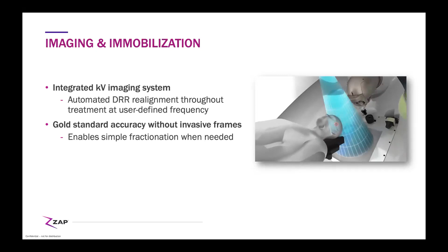The targeting system uses this amorphous silicon camera that you see in the back, as well as this KV source. Together, they generate real-time images that are then correlated against digital reconstructed radiographs made from the patient's original CT. So the original CT is used to generate DRRs, predicting patient position and orientation. Then real-time images are correlated against that library of DRRs and allow us to establish with sub-millimeter accuracy where the patient is positioned in space. You get frame-based targeting accuracy without frames.